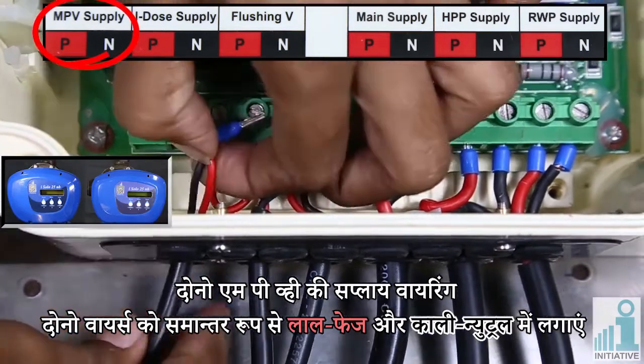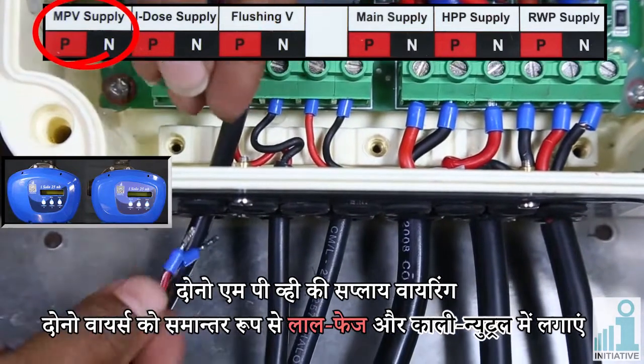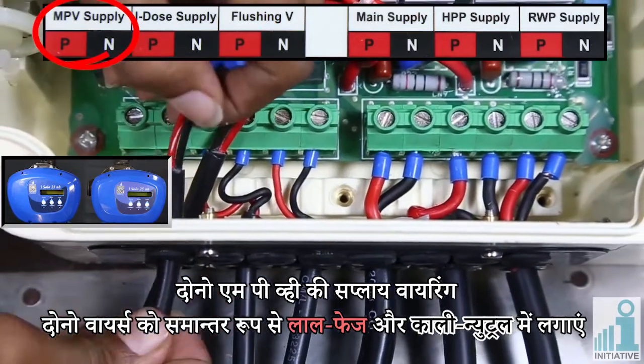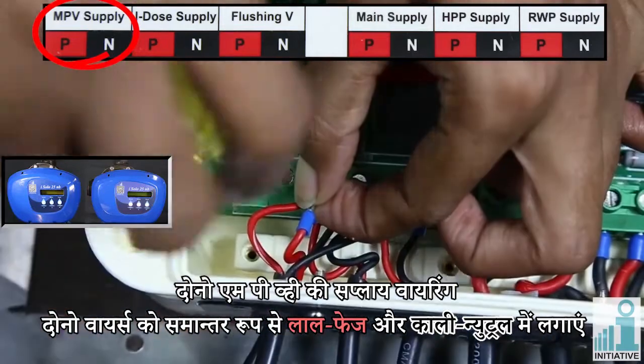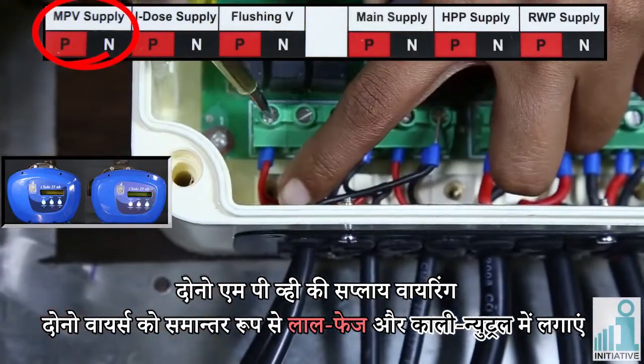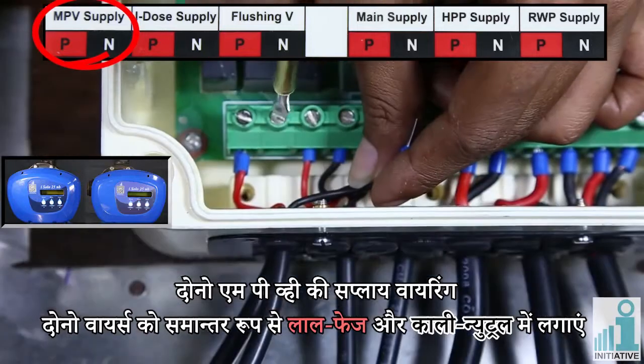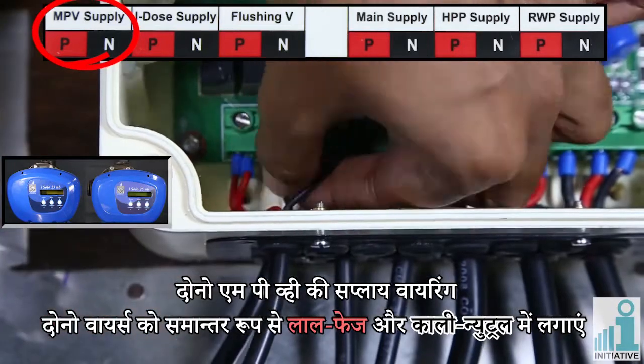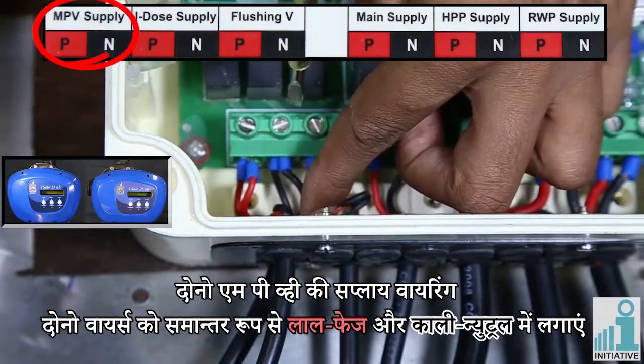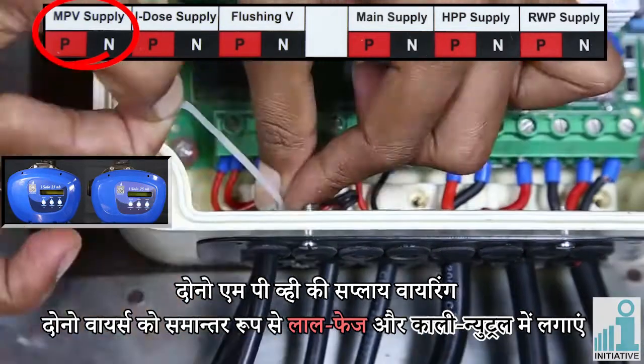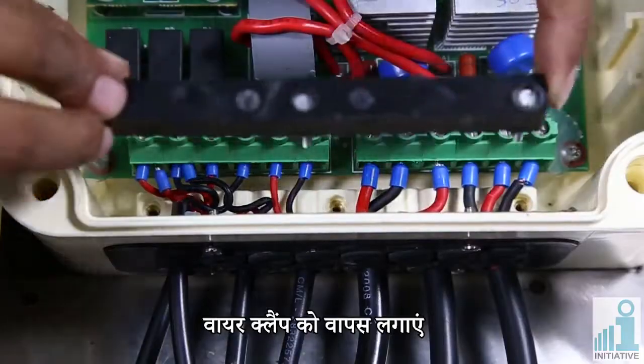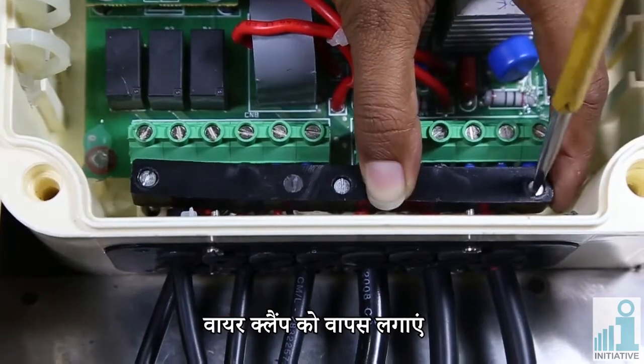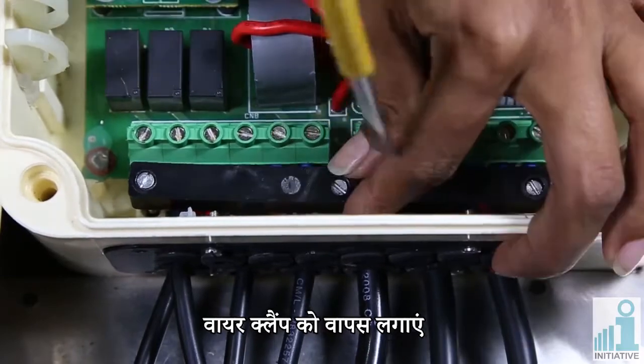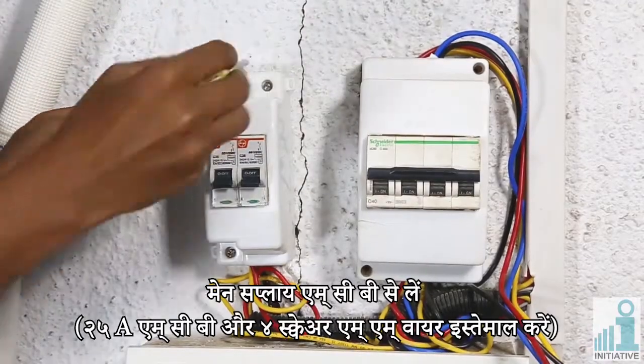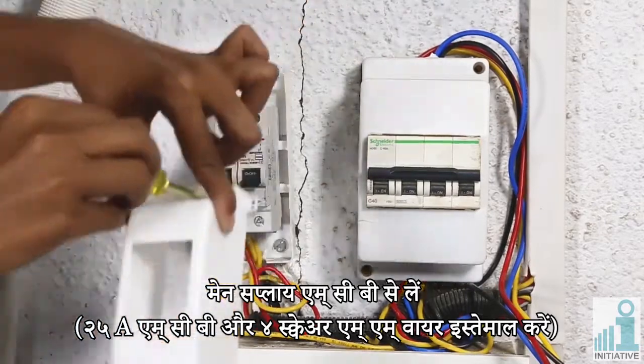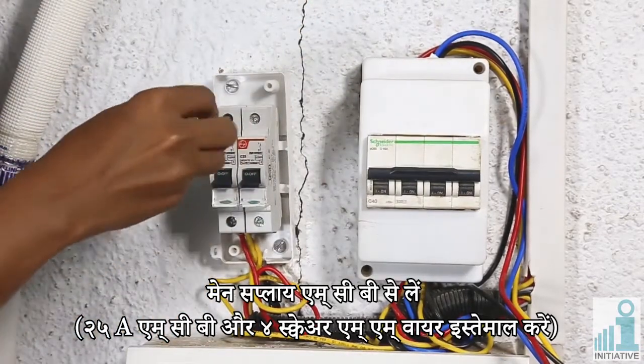Both MPV supply wiring. Connect both wires red in phase and black in neutral parallelly. Fix the wire clamp. Take main supply from MCB. Please use 25 ampere MCB and 4 square mm wire.